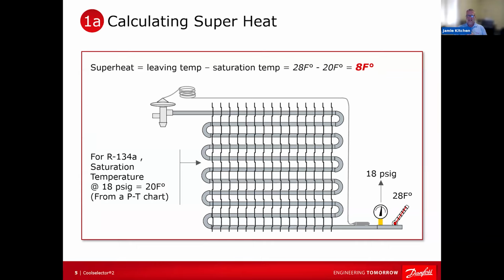So what you're seeing here, when you're calculating superheat, essentially tells you one thing: how much refrigerant mass you have compared to your load, right? If you have less refrigerant compared to your load, you're going to run out of liquid sooner in your circuit, which means you have 100% vapor. Now that vapor has more highway, more time to pick up heat, because remember, you're probably blowing in a medium temp refrigeration system 12, 15, maybe 20 degrees above your refrigerant temperature. You're going to pick up some heat. And so the longer you're a vapor, the more heat you pick up.